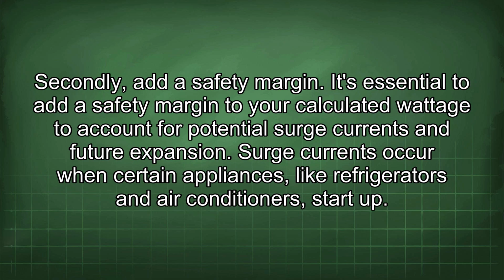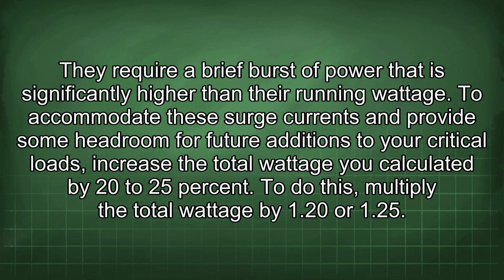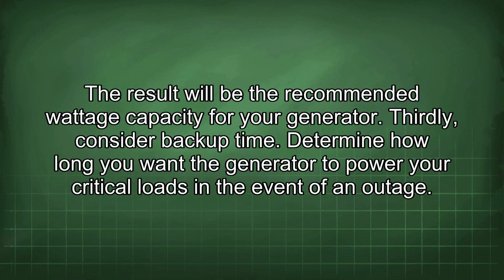Surge currents occur when certain appliances, like refrigerators and air conditioners, start up. They require a brief burst of power that is significantly higher than their running wattage. To accommodate these surge currents and provide some headroom for future additions to your critical loads, increase the total wattage you calculated by 20 to 25%. To do this, multiply the total wattage by 1.20 or 1.25. The result will be the recommended wattage capacity for your generator.